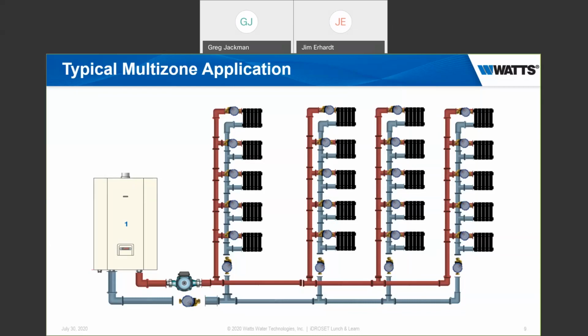Then we look at the actual vertical stacks themselves. If you see, there's also a balancing valve on the return going back on each stack, going back to the main return, going back to the boiler. If we only had the stack on the left, then we wouldn't have to worry about having that extra balancing valve on the return of the stack.